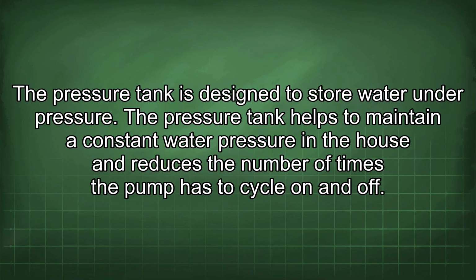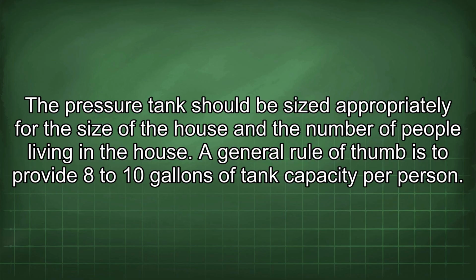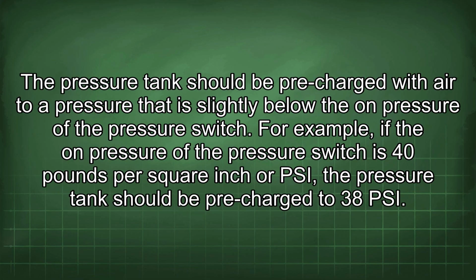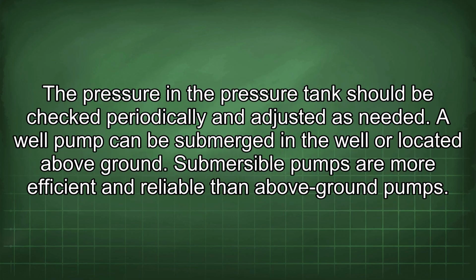The pressure tank is designed to store water under pressure. The pressure tank helps to maintain a constant water pressure in the house and reduces the number of times the pump has to cycle on and off. The pressure tank should be sized appropriately for the size of the house and the number of people living in the house. A general rule of thumb is to provide 8 to 10 gallons of tank capacity per person. The pressure tank should be pre-charged with air to a pressure that is slightly below the on pressure of the pressure switch. For example, if the on pressure of the pressure switch is 40 pounds per square inch, or psi, the pressure tank should be pre-charged to 38 psi. The pressure in the pressure tank should be checked periodically and adjusted as needed.